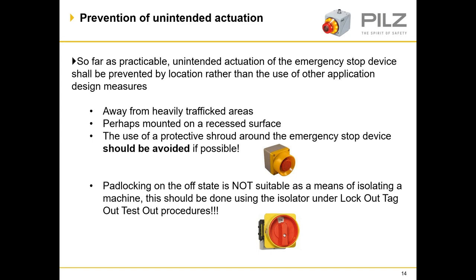Padlocking of an emergency stop in the off-state is not an effective method to ensure the machine stays safe and motionless, as this could fail. If you wish to isolate the machine, then an isolator should be used along with lockout, tag out, test out procedures. The red and yellow switch disconnector can be used as an emergency stop device, which the next slide addresses under EN 60204 section 10.7.4.